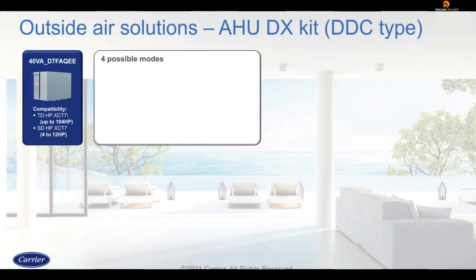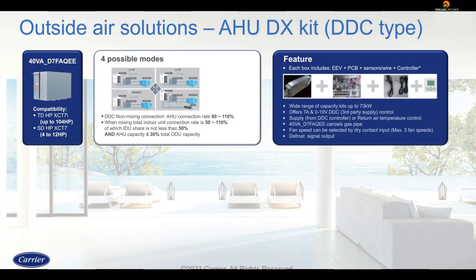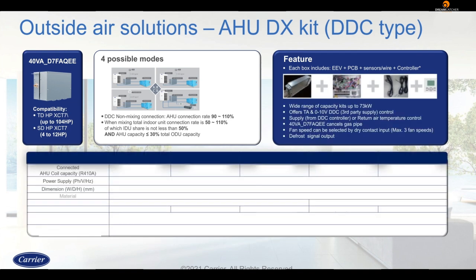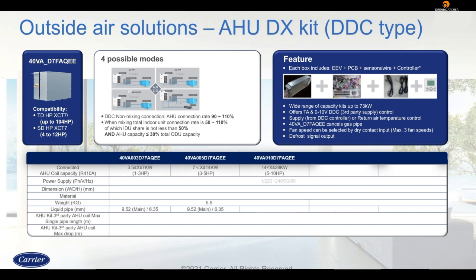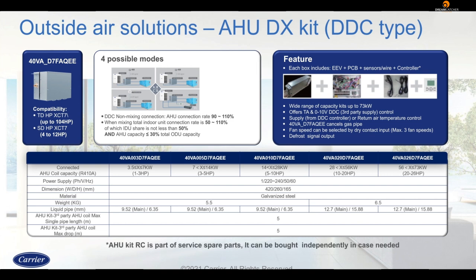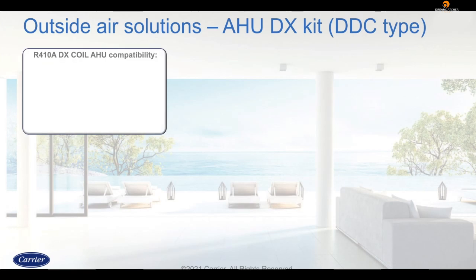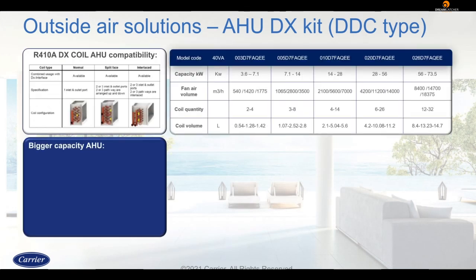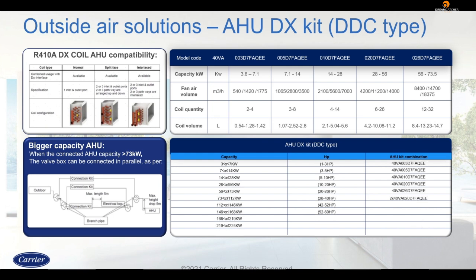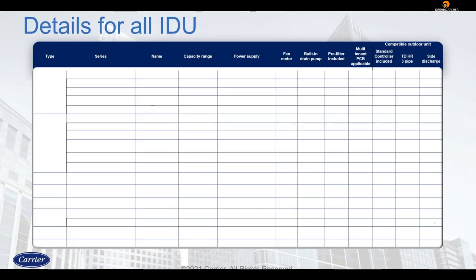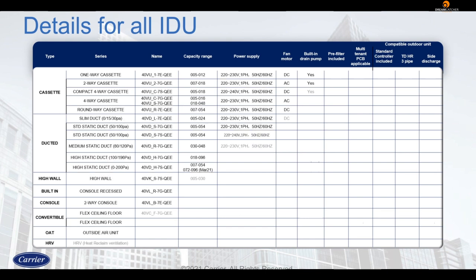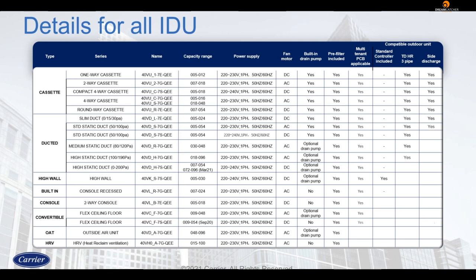DDC type AHU kit comes with an expansion valve, PCB, sensors and wires, and also has a controller. It offers 4 possible modes of connection and gives a more accurate solution than the TA type. It can be controlled with either supply air temperature or return air temperature. It follows the same rule of combination as TA type does, and it can connect up to 104 HP VRF system, and also the side discharge 2 fan system from 4 to 12 HP. When connected to a bigger capacity AHU of more than 73 kilowatts, the kit needs to be connected in parallel, as shown here. Here is a roundup of all the types of indoor units that make the XCT7 VRF system so efficient and flexible.